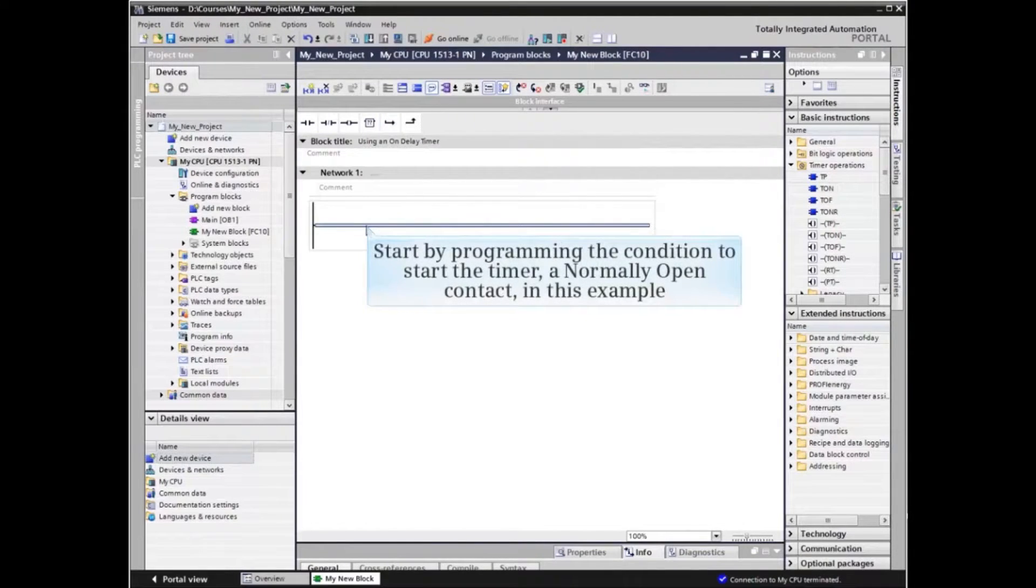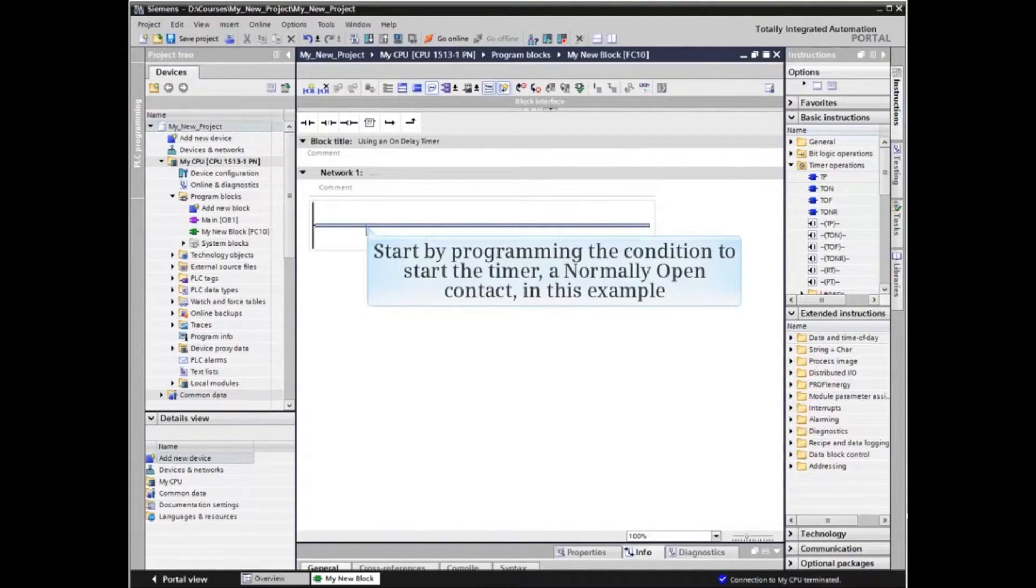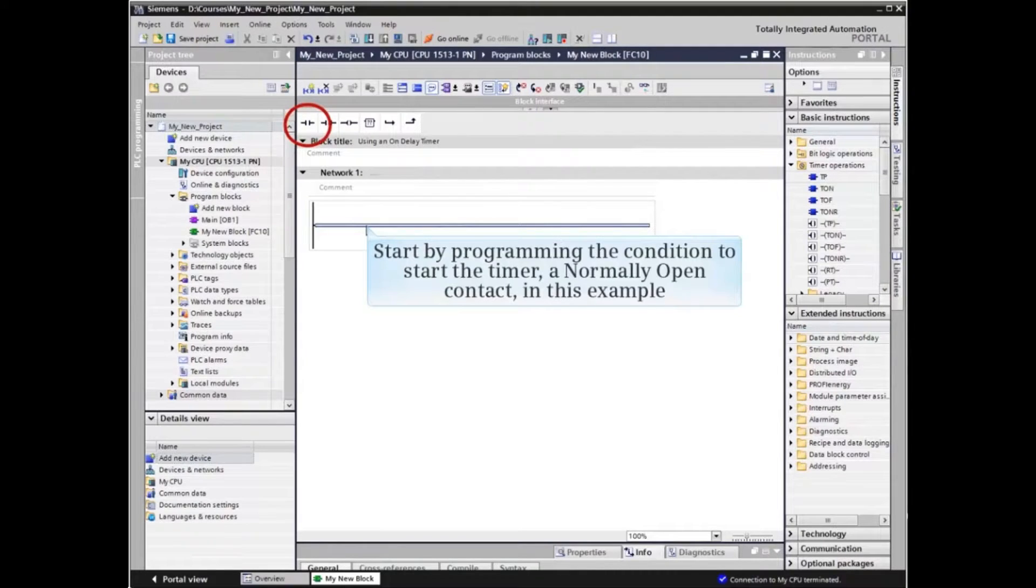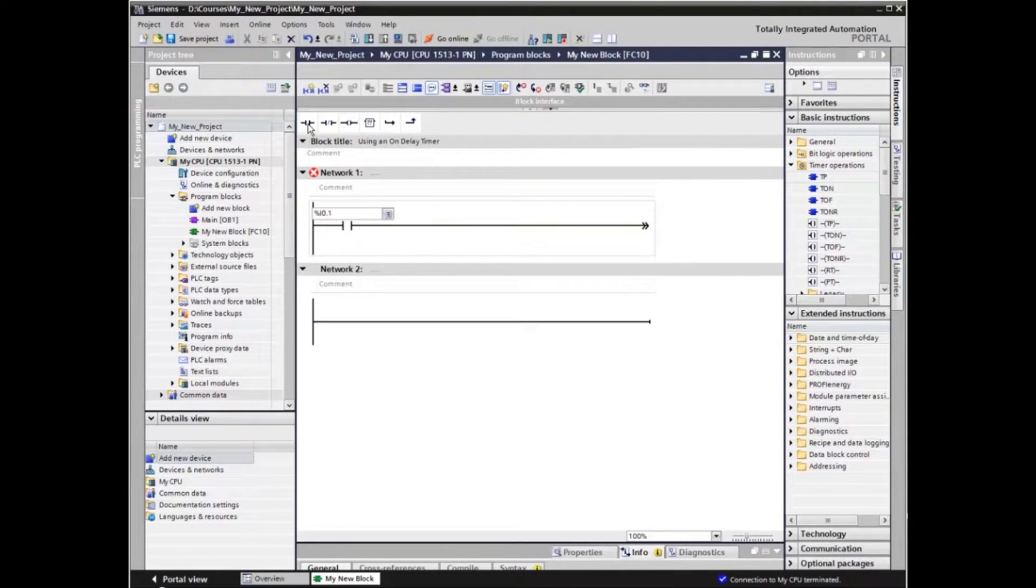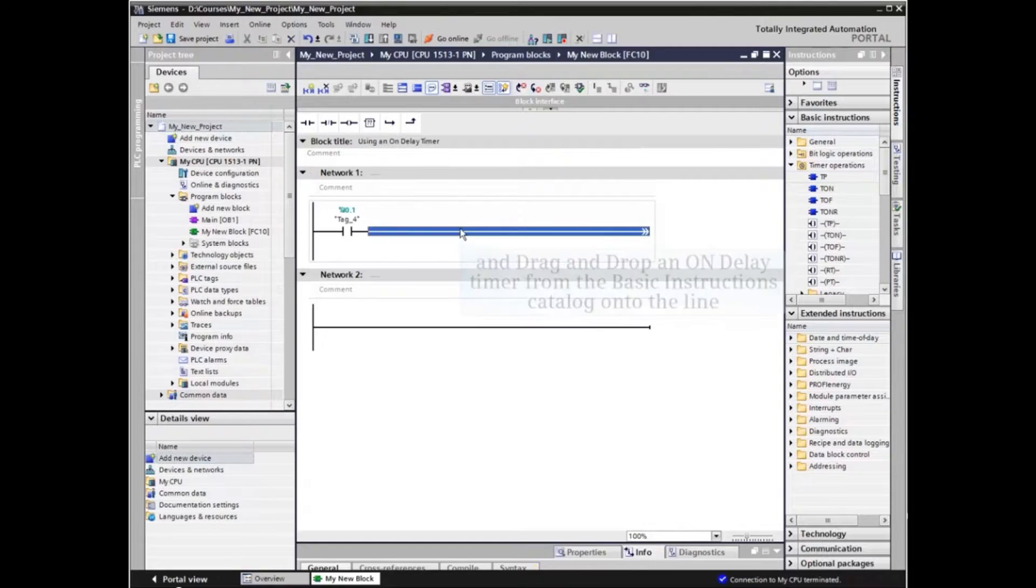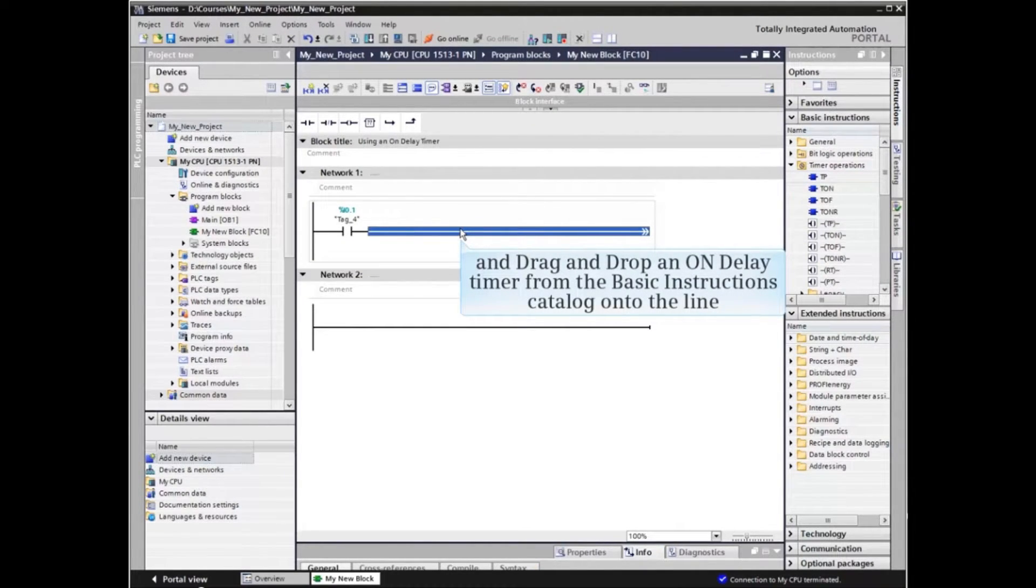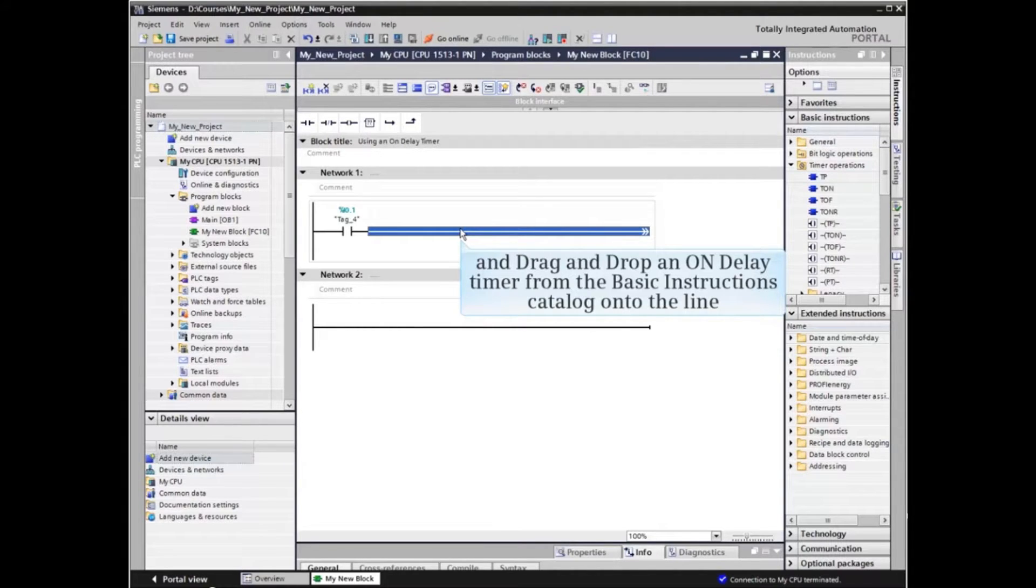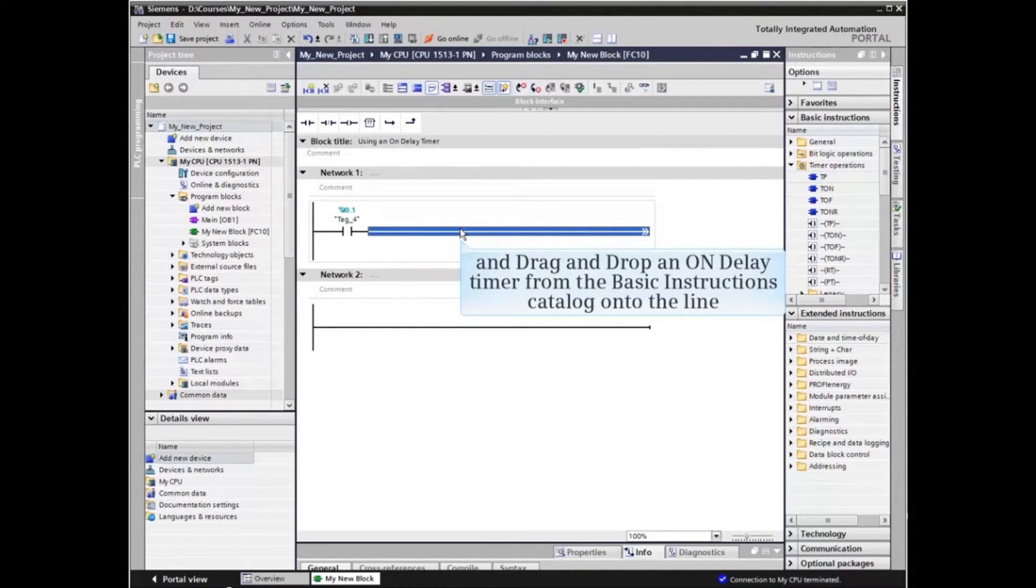We start by programming the condition to start the timer, a normally open contact in this example. We then find the on-delay timer, a TON element, in the basic instructions catalog and drag and drop it onto the line.